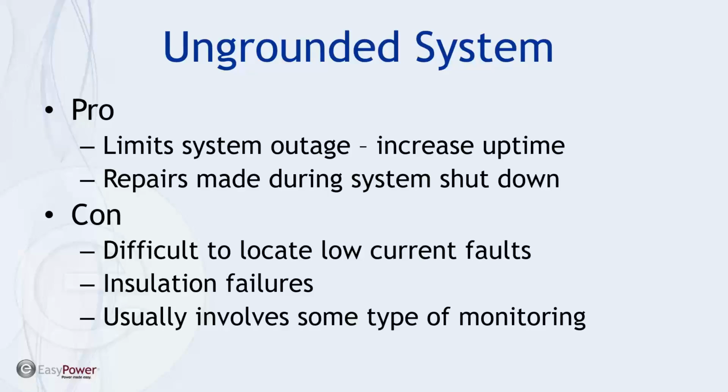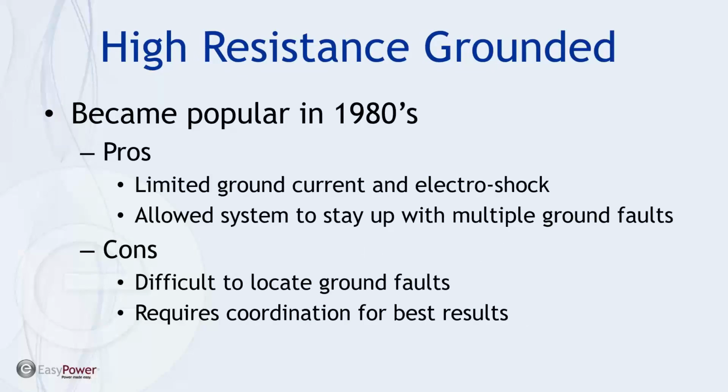Today, when we have an ungrounded system, frequently it involves some sort of monitoring so you can do a health check on the system from time to time. In the early 80s, so there's kind of a segregation here between resistance grounding and high resistance grounding.